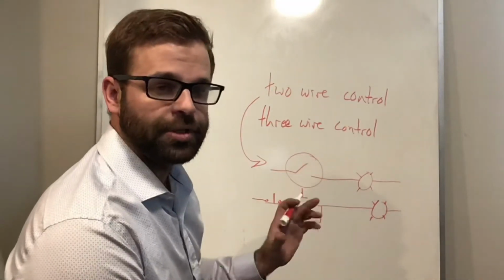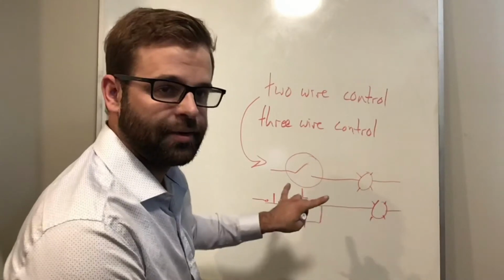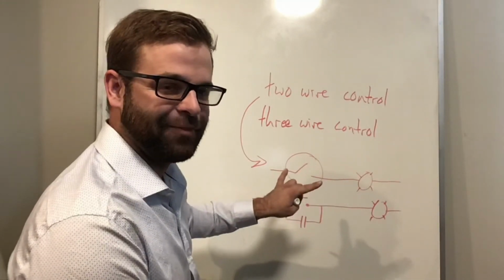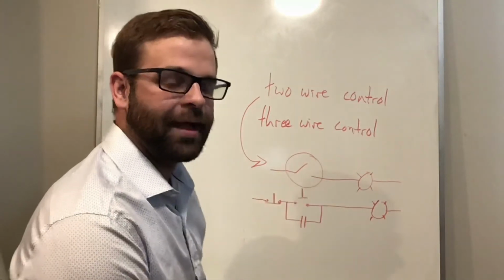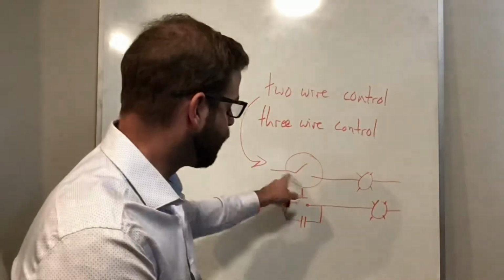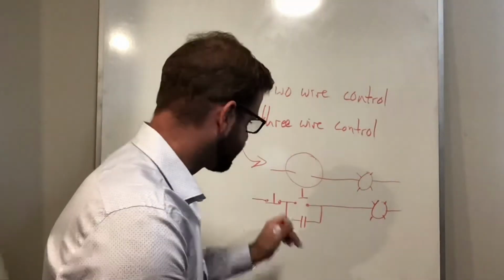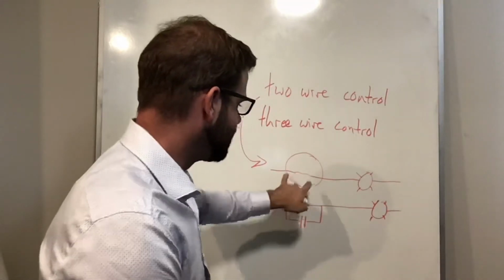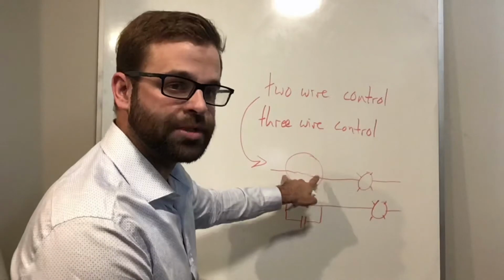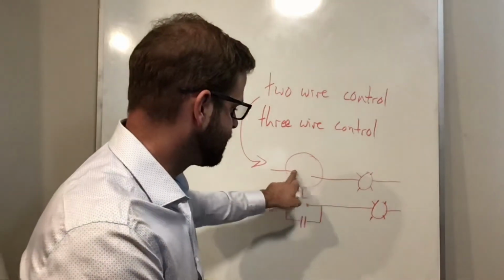When the toggle switch is open and I put a meter across, I would see a resistance of OL. When I close that switch and put a meter across those 2 points, it would read 0. So a closed switch measures 0 ohms, and an open switch reads OL.